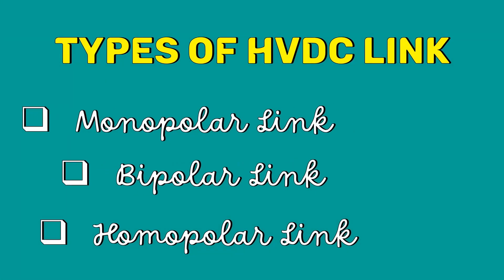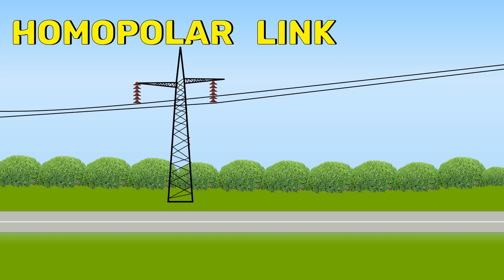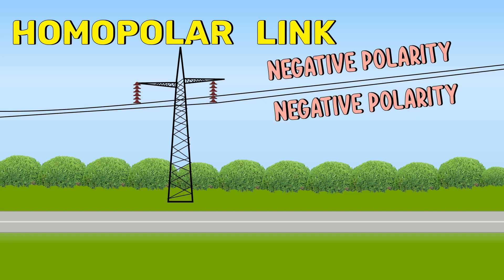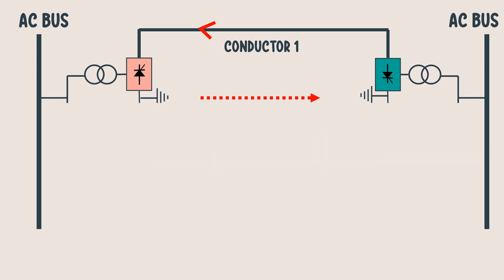Now let's move on to the homopolar link. Homo means same. As the name indicates, the homopolar link has two or more conductors, all having the same polarity. Usually, negative polarity is preferred to reduce radio interference. Here, the ground acts as a return path. If a fault occurs in one conductor, the converter equipment can be reconnected so that the healthy conductor can supply more than 50% of the rated power.